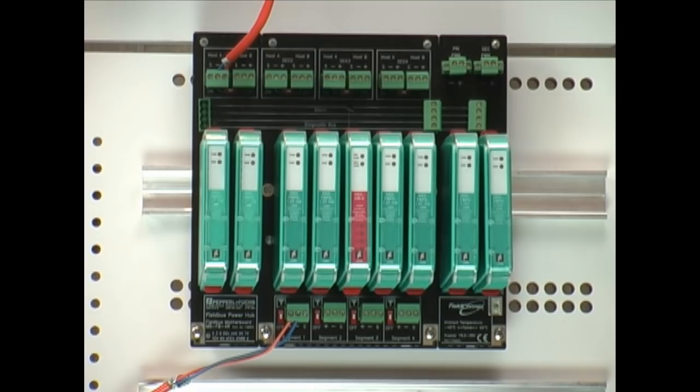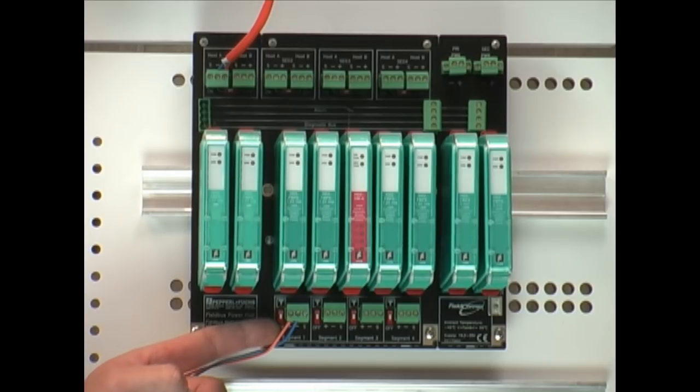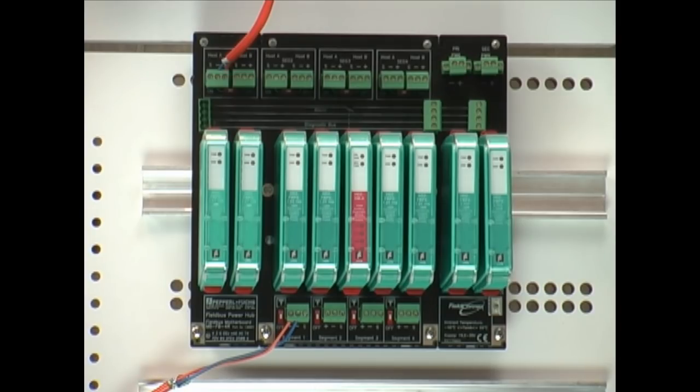Now the various power supplies available from different manufacturers offer redundancy of the power supplies as well as usually a built-in selectable terminator. Each Foundation Fieldbus segment needs two terminators one at each end of the segment and so having it built into your power supplies is a convenient way to make sure that that's included.